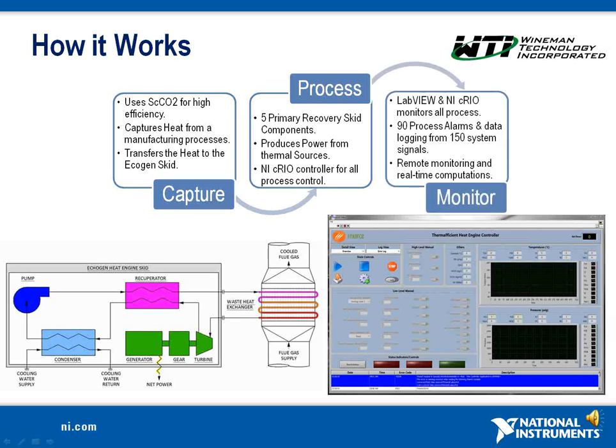The control and data acquisition for process monitoring was developed utilizing LabVIEW and CompactRIO. System requirements include acquiring data from more than 75 sensors and controlling more than 40 devices through Modbus, analog, and digital signals. Additionally, we use multiple PIDs to control the system based on various readings, including system pressure, fluid heat, system mass, flow, and turbine load at different locations within the system.